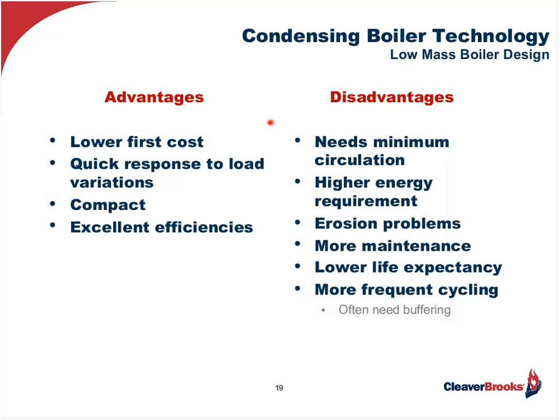So let's talk about low mass boilers and their advantages and disadvantages. They do have a lower first cost because they don't contain that vessel with the mass of water. There's not as much material. Because there's not a lot of water in them, they will be very quick to respond to load variations, and they're very compact. And because they're a condensing boiler, if they're operated correctly, they will have excellent efficiencies. The disadvantages, and this is all due to their lack of mass, is they need a minimum circulation.